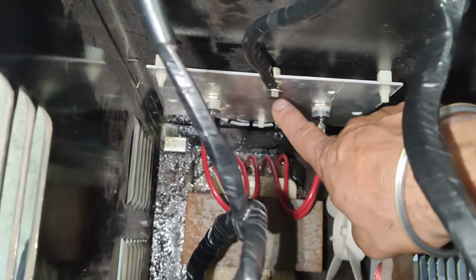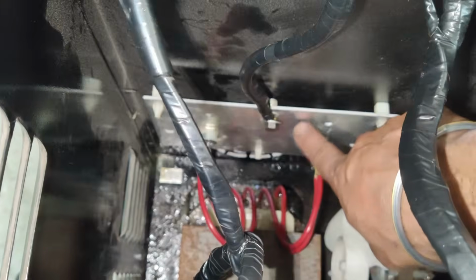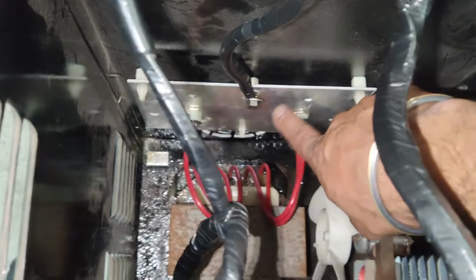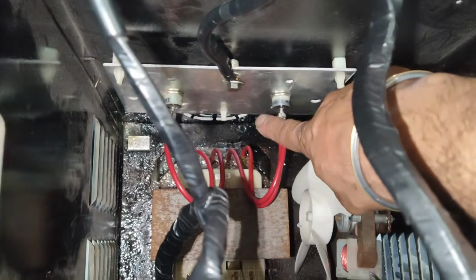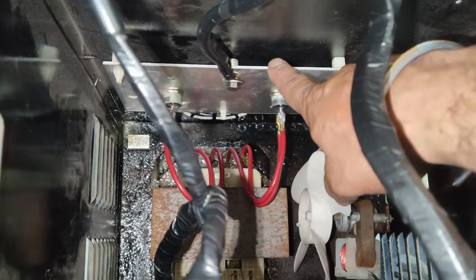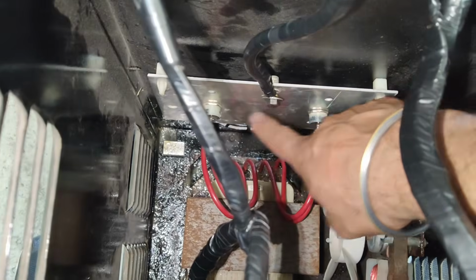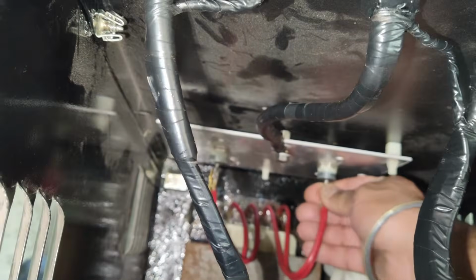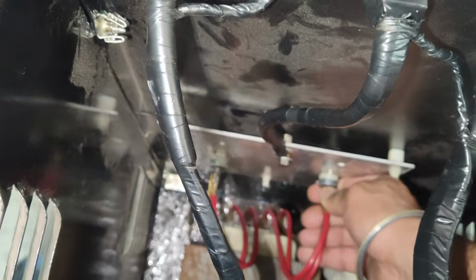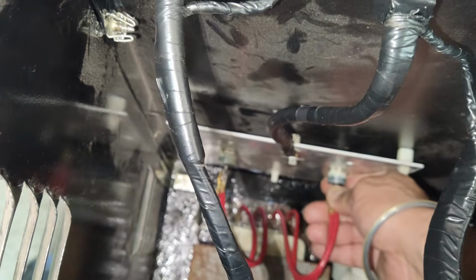Now, when I test at this terminal or right onto the heat sink here, I have no voltage. You should have your DC voltage at this plate here, which I do not. Most likely my diodes are not working, because as I move these around, this thing actually came right off. You can see how that's kind of broken off on me, and I was able to push it back on.